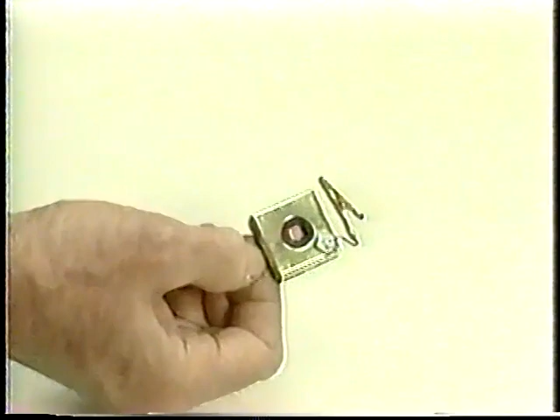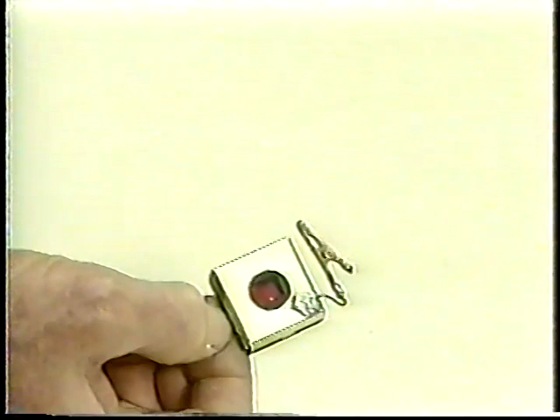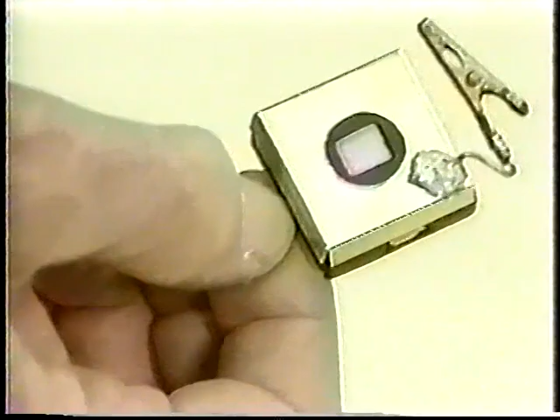For the rest of this demo, the camera will be zooming in on these items in my hands. Here's the static event detector again. I'm holding it by its base, and now a piece of highly charged polystyrene foam will be brought up to it. And as you see, the detector was zapped by an air discharge through a considerable amount of space. The polystyrene foam never touched it, and in fact, static fields will damage devices at a distance in a similar manner.